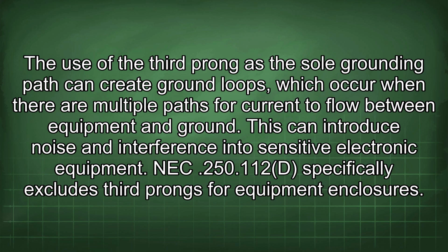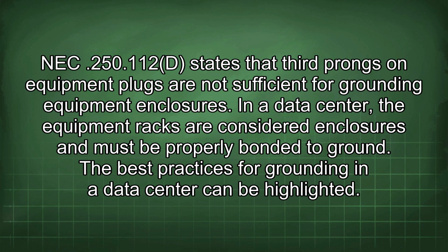NEC 250.112(D) specifically excludes third prongs for equipment enclosures. NEC 250.112(D) states that third prongs on equipment plugs are not sufficient for grounding equipment enclosures. In a data center, the equipment racks are considered enclosures and must be properly bonded to ground.